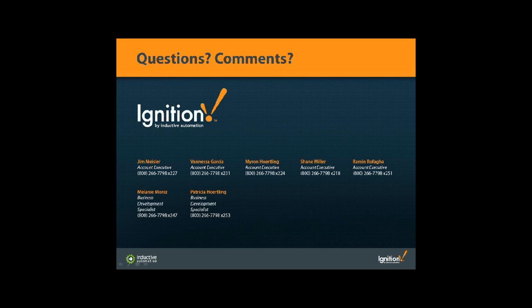Travis, why don't you comment too, since you've got experience with a variety of projects over the years. Ignition has a lot of built-in drivers for different PLCs, and a lot of the big ones are supported. We have the Allen-Bradley Ethernet suite of drivers for CompactLogix, ControlLogix, MicroLogix, PLC-5, SLC-500, 504, ENI module, etc. We also have Modbus TCP and Modbus RTU over TCP, and Siemens S7 1200, 300, 400. Those are all the Ethernet devices Ignition supports natively, and those drivers are free and included with Ignition. Ignition also supports OPC to the core, so besides our own drivers and OPC server, you can connect to any third-party OPC server such as RSLinx, Kepware, Matrikon, etc., and bring data from those into Ignition as well. So you can bring in data from pretty much any PLC as long as there's an OPC server, though a lot of people like the built-in drivers that come with Ignition.